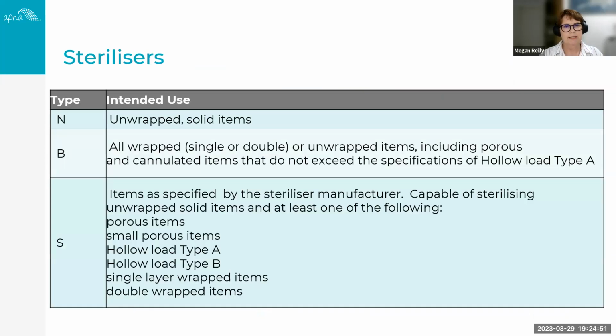Now, your sterilisers, it's critical to know what type of sterilizer that you have and that you're using the appropriate sterilizer for the RMDs that you are reprocessing. So when we purchase sterilizers, or in fact any reprocessing equipment, whether it's a washer disinfector, an ultrasonic, whether it's a heat sealer, whether it's your biological indicator machine, then you need to make sure that it meets the existing Australian and New Zealand standards and that it has been TGA approved. So N-class sterilisers are only suitable for unwrapped solid items. So we don't tend to see these types of sterilisers. They've more or less become defunct.